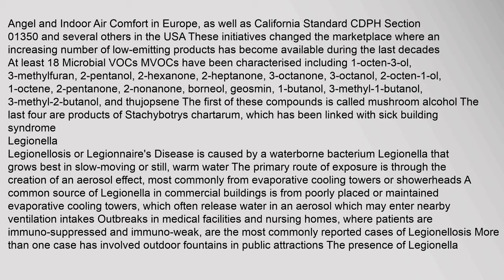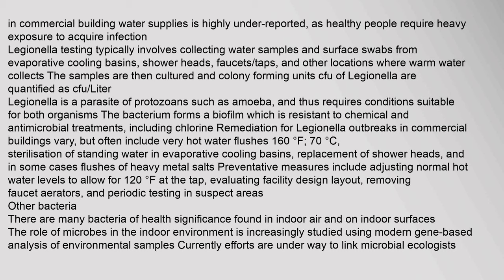Legionellosis, or Legionnaires' disease, is caused by a waterborne bacterium, Legionella, that grows best in slow-moving or still, warm water. The primary route of exposure is through the creation of an aerosol effect, most commonly from evaporative cooling towers or showerheads. A common source of Legionella in commercial buildings is from poorly placed or maintained evaporative cooling towers, which often release water in an aerosol that may enter nearby ventilation intakes. Outbreaks in medical facilities and nursing homes, where patients are immuno-suppressed, are the most commonly reported cases.